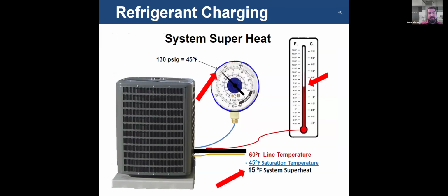So what it would actually look like in the field. This is your gauge. You would read all gauge sets, just for anybody that doesn't know. They have the saturation temperatures for different refrigerants on your gauge set. Your gauge set would be appropriate for the refrigerant that you're working on. You would have those saturation temperatures right on the gauge so that you can see at 130 psi, saturation temperature is 45 degrees. If you measure 60 degrees on your suction line, you would have 15 degrees of superheat.